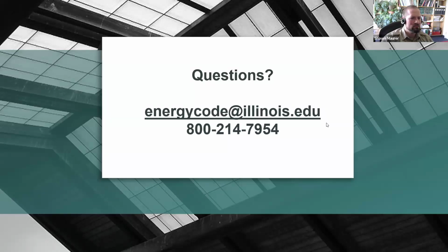Question about the receptacles. If at least 50% of receptacles need to be controlled, if you're using split receptacles, wouldn't that mean all of them need to have the top receptacle controlled? I believe we've come down in our office as that is the strict interpretation, yes, from some conversations we had. However, we're not exactly sure how that's going to be interpreted within the field.